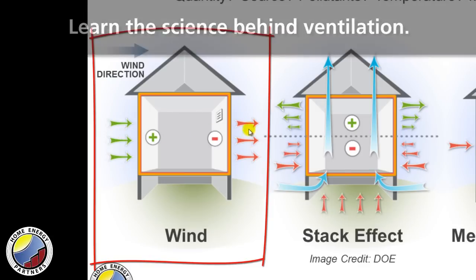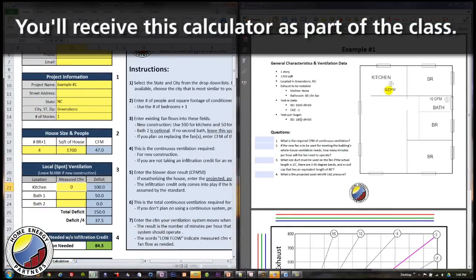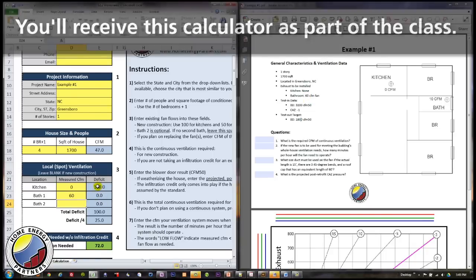I'll leave that at zero because the fan is not going to be replaced, not on the agenda, so I'll leave the kitchen at zero. The bathroom, however, we're going to be installing a 60 CFM fan, so I can type in 60 and notice that I have a 100 CFM deficit here for the kitchen.